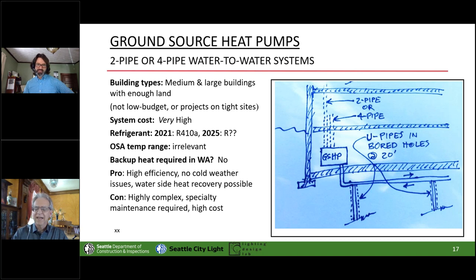This is the answer. And as far as making connections work, I pictured maybe you could have a trench every 60 feet or so that would pick up one row of wells directly below it and a row on either side 20 feet out, whereas all the connections from that pipe to the lateral that would take it to the heat pump would be made in a trench that you could access. Because that's really the only thing that's going to break in one of these, would be where you sewed them together. So yeah, and it's heat fused piping, so it's really durable.